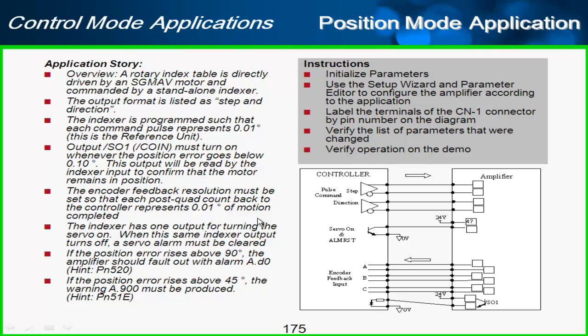The encoder feedback resolution must be set so that each post-quad count back to the controller represents 0.01 degree of motion completed. So you see how that works here, the controller is going to send a pulse to the amplifier and we want the encoder feedback, when it's read as quadrature, encoder feedback to also show that that 0.01 degree of motion has taken place.